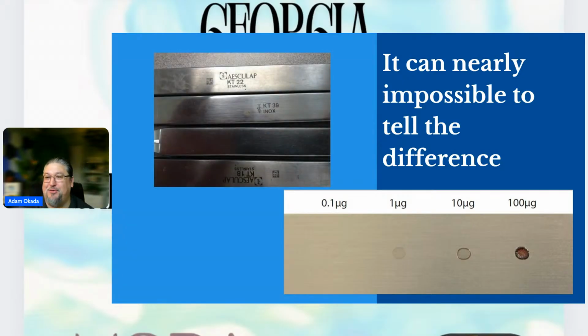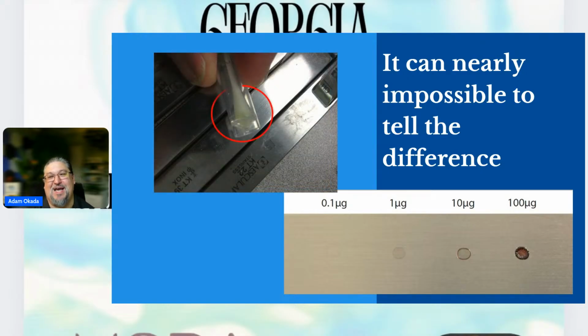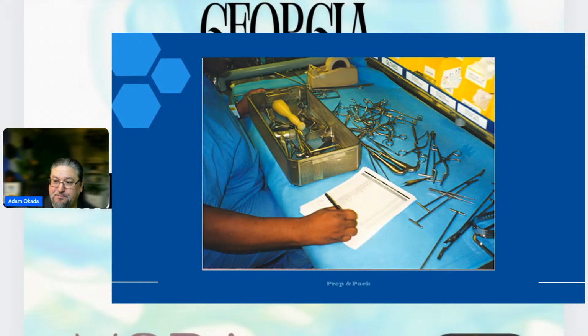And the reason that blood or rust is not a funny game is because this instrument that we were looking at that was discolored, when we tested it, it actually did test positive for protein. So there was some kind of biological material in there. And that's the scary thing about blood or rust. If you're playing that game in your department and you have a lot of discolored instruments, you're having a problem usually with water quality, but it could be a problem where it's not cleaning effectively with your equipment or at the manual cleaning steps. So really start to look into if you have issues with staining, that is something that needs to be taken care of.